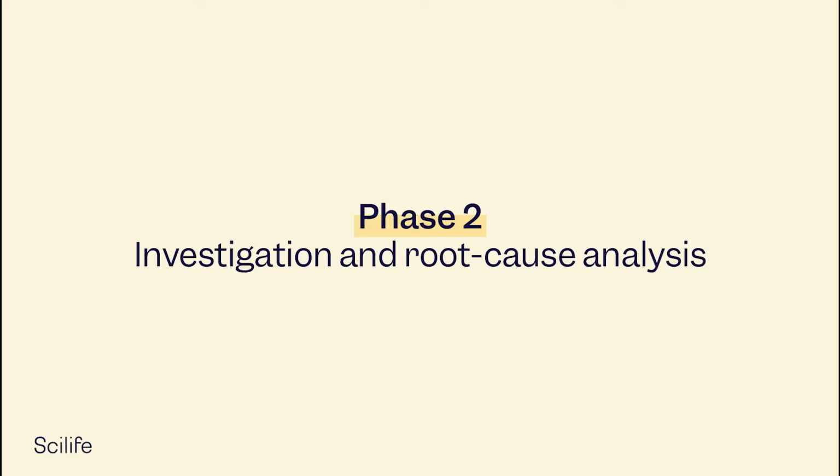The type of event is identified: incident, minor, major, or critical, based on risk management system principles, and the root cause is reported if it is clear. This phase is usually one of the most important and the most difficult in the process. If the event is major or critical and the root cause is still unknown, then a full investigation should be performed using root cause analysis tools. Typically, a full root cause analysis is unnecessary if the event is categorized as incident or minor.